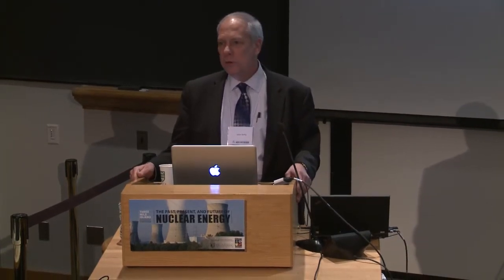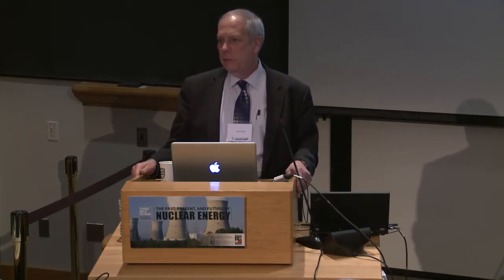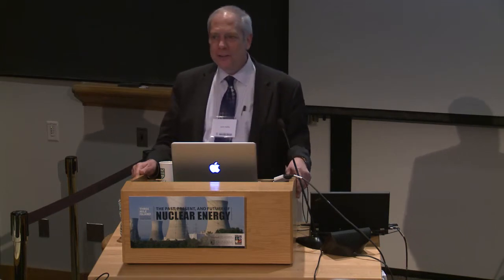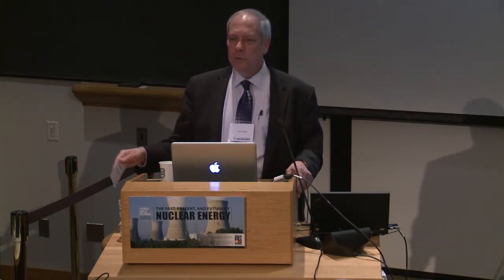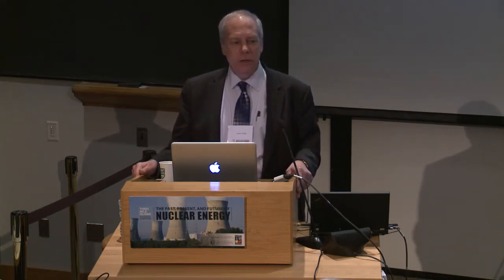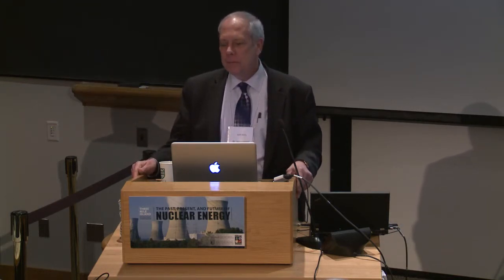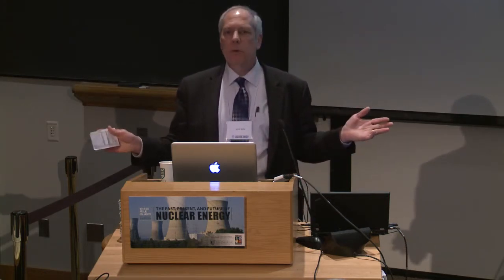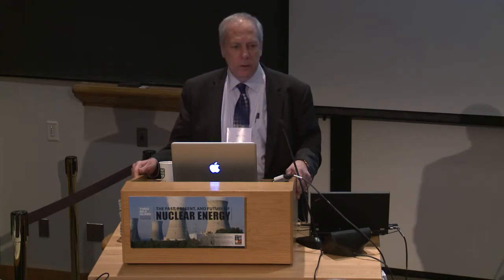And we're driving into work and we hear about this earthquake and tsunami, and all of us kind of realize this is not good. They need to be getting water into the core as soon as possible, because the word was out that they had lost power, et cetera. I've been to Fukushima. I've been on top of the reactor building that was blown up. And you can see the towers had collapsed. They had lost their power. They would have probably been okay had the tsunami not come and flooded their diesel generators, which caused the complete loss of power.